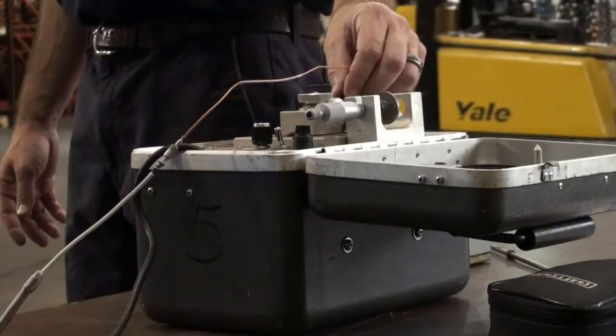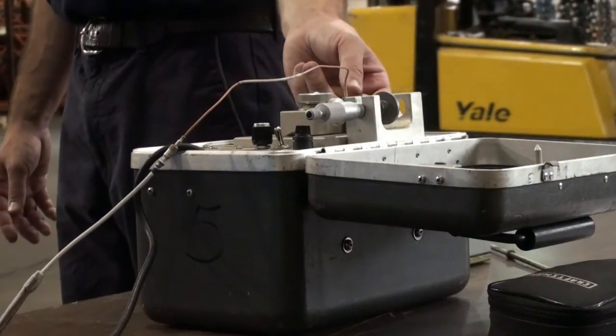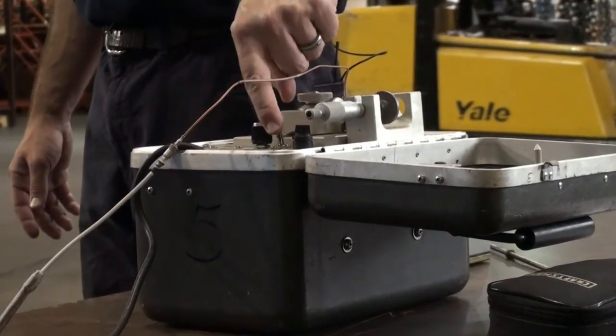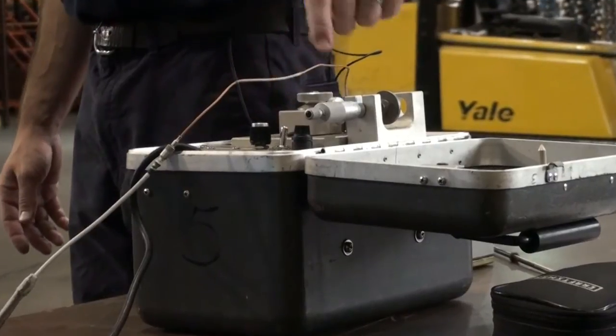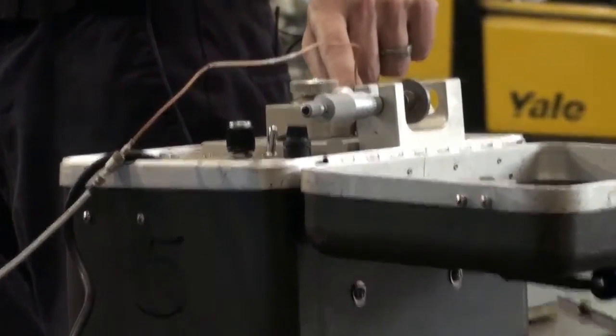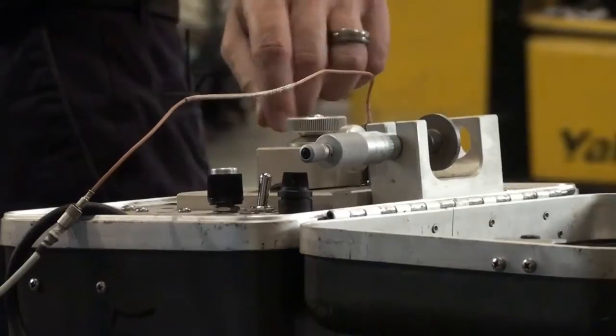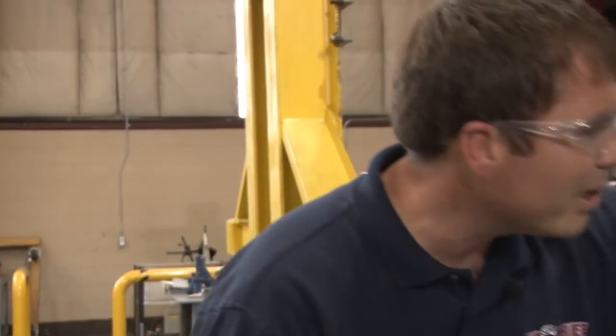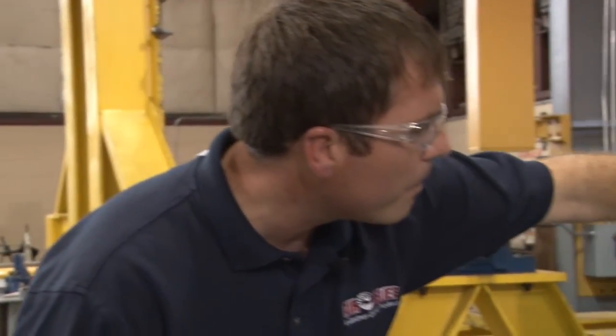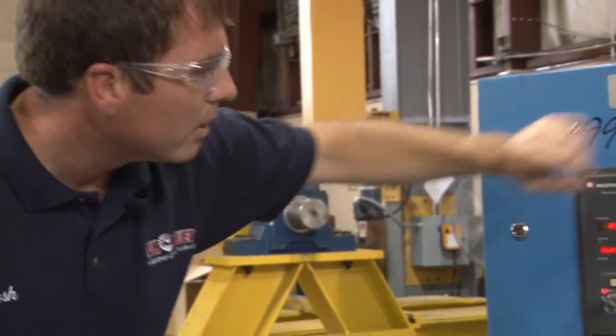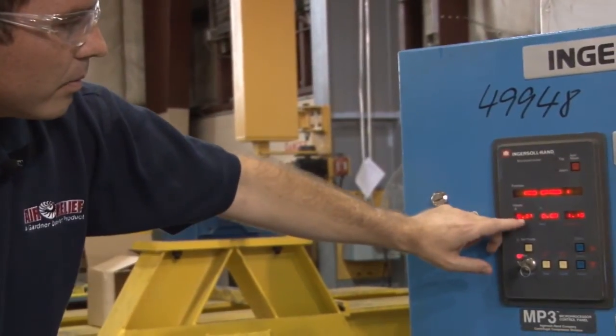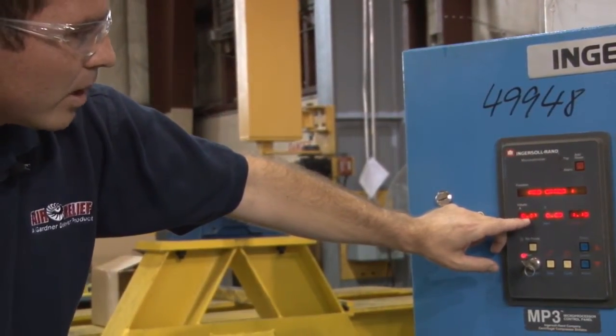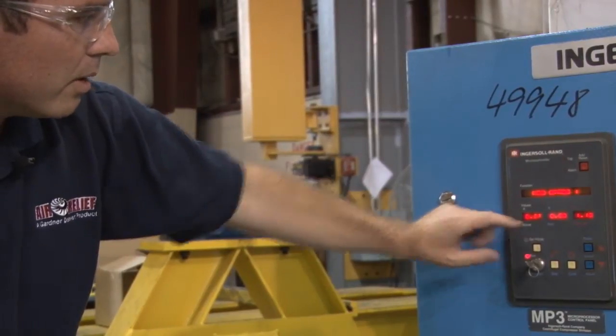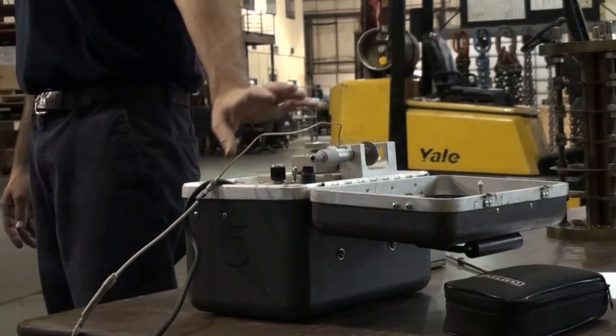I've set this one up. I've got a 40 thousandths probe gap here, and I'm going to turn this on. This dial here will represent a spinning shaft in the compressor. You can see over here, we actually have a 0.37 or almost 0.4 of a mil of vibration simulated with this equipment.